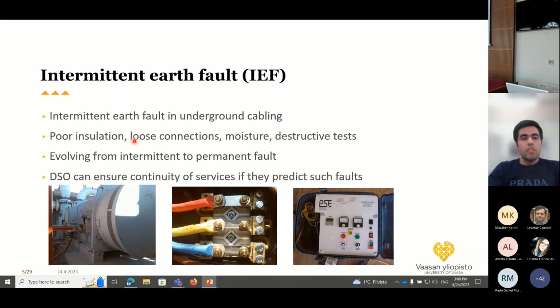Another thing, as I mentioned, is a loose connection, maybe in the terminal of a motor, which is shown here. Especially in the commissioning phase, commissioning engineers tend not to tighten this because they are always opening and closing, and most of the time, even at the beginning of a project, it can be problematic. So it's a good idea to pay serious heed to such a thing to avoid an otherwise grim future in terms of earth fault or intermittent earth fault.